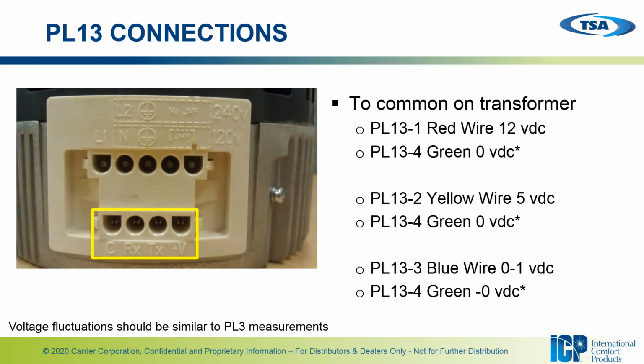And again, here's a look at what your readings should be between all of the wires. Between the red wire and green wire, you should have 12 volts DC. Yellow wire and green wire, you should see 5 volts DC. Blue wire and green wire, 0 to 1. Again, it's probably going to be hovering just over 0.